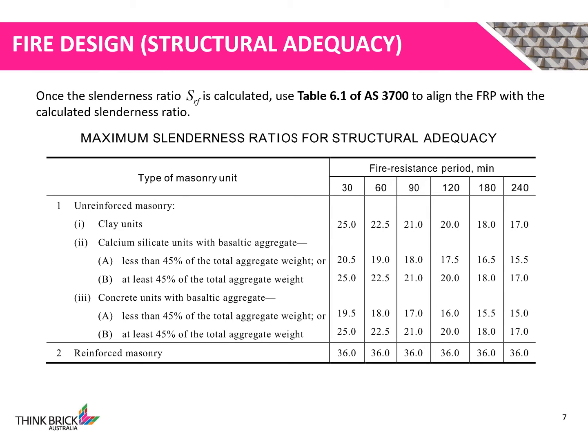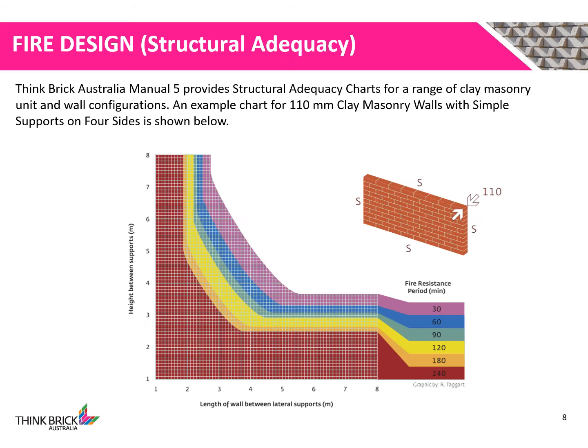Once we've determined our slenderness ratio from the formulas provided, we can use Table 6.1 of AS 3700 to align the fire resistance period with the calculated slenderness ratio. Think Brick Australia Manual 5 provides structural adequacy design charts for a range of clay masonry unit and wall configurations. You may use these to empirically determine the fire resistance period for structural adequacy in lieu of the mechanistic process shown beforehand.